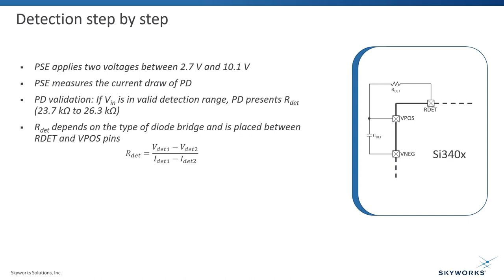As we can see, R-det is calculated by taking the difference of the two measured voltages divided by the measured current difference. We call this differential resistance measurement, which determines the resistive slope and allows static voltage offsets in the PD.